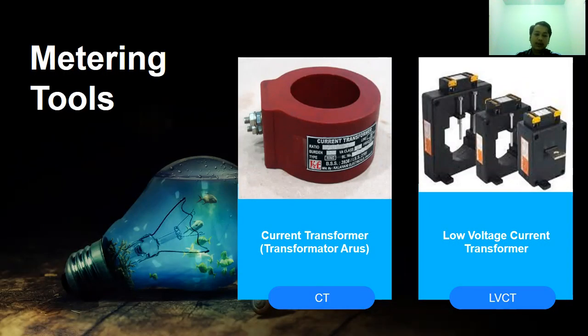Here we have metering tools. The metering device cannot be directly installed because the metering device can be broken by high current flow. That is why we need a device, a current transformer and low voltage current transformer. These tools are used to secure the measuring device by reducing the amount of current that enters the metering device. So the metering device will not be directly exposed to the high current. The metering device that has been installed on the network will be connected to the system by SCADA.